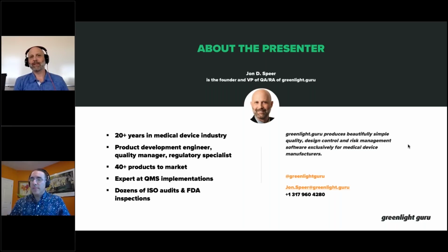Now, there are a couple of things that are in place. We've got this program in the world now called the MDSAP, Medical Device Single Audit Program, of which FDA, as well as a few other regulatory bodies throughout the world, basically defined in that program. You could go through an MDSAP audit. MDSAP audits generally would mean that you're also being audited to ISO 13485:2016 as well. And so going through that MDSAP, you're getting an ISO audit, but that's also satisfying the FDA needs to be able to demonstrate that your quality system is compliant with the FDA regulations.